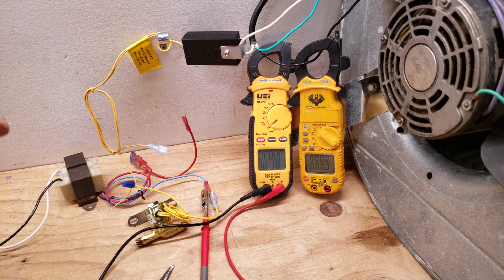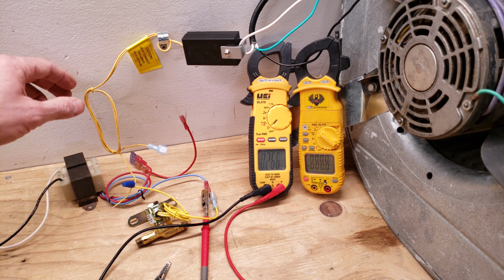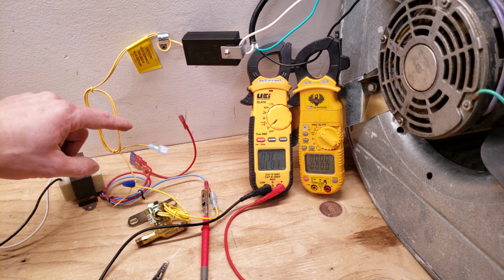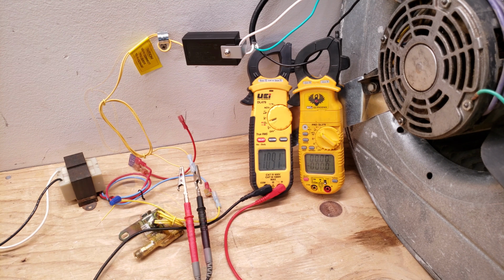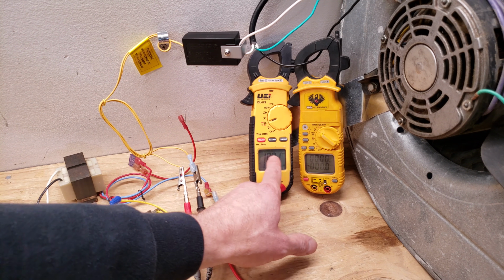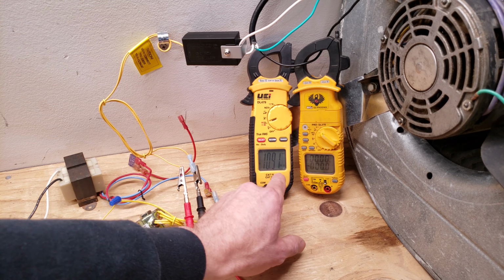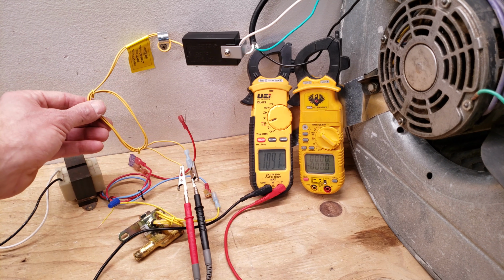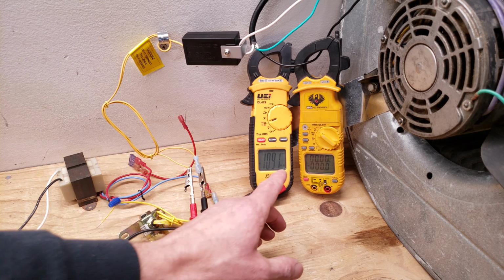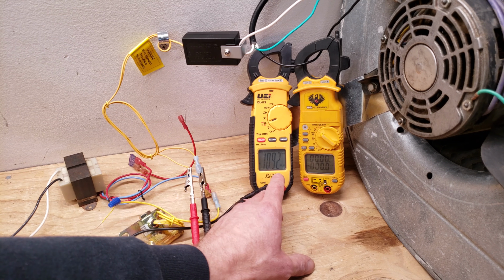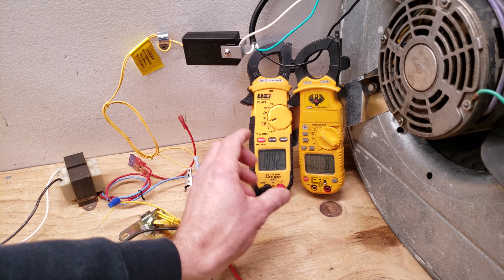Now I'm going to turn the power off to the transformer, and we're going to read a resistance value on these two wires for the relay. So you see we're reading mega ohms. So you're always going to read some type of mega ohm reading when the contacts are in an open position. That's not going to allow any voltage across there. It has such a high resistance value.